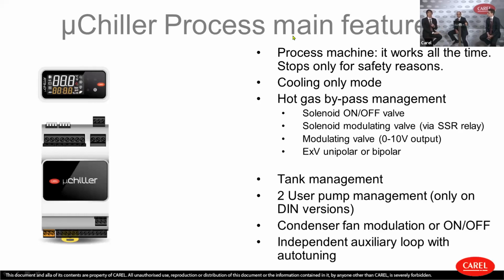There's one addition here: the BLDC compressor can work together with the hot gas bypass. It might look strange, but it's the best way to be very precise and efficient. Any compressor has a minimum speed, of course. But one thing is to modulate via compressor, another is via valve, whose response is much faster. So if you need a very fast response and want to keep the unit on when close to the minimum, controlling very precisely in some medical applications and so on, you have the freedom to set up the parameters of the hot gas bypass intervention the way you like. I think it's a very nice thing.